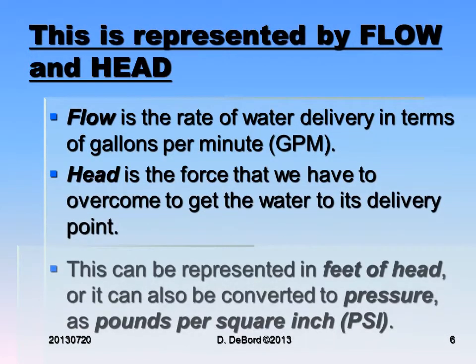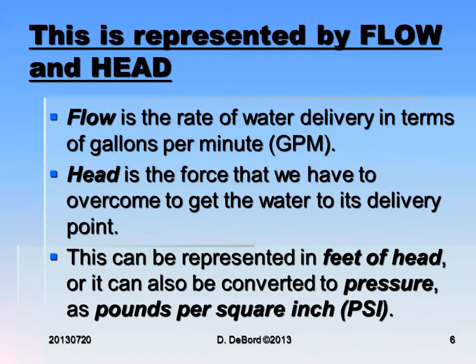The output is represented by both flow and head. Flow is the rate of water delivery, and here we're talking about GPM, gallons per minute. Head is the force that we have to overcome to get the water to its delivery point, measured in feet of head. This can also be converted to pressure as pounds per square inch, or you could use metric equivalents.